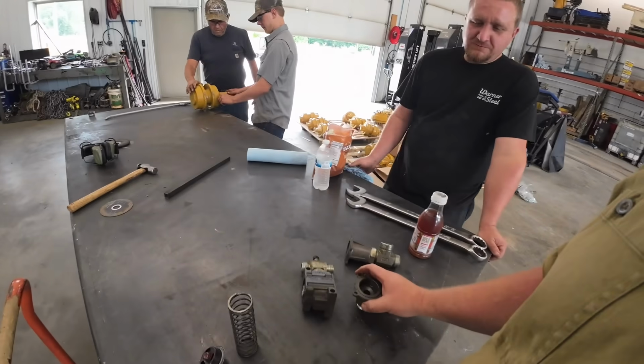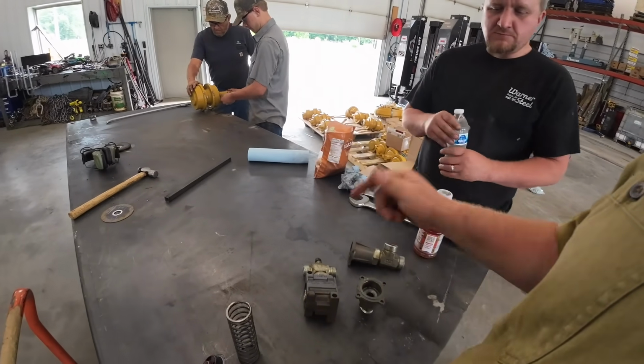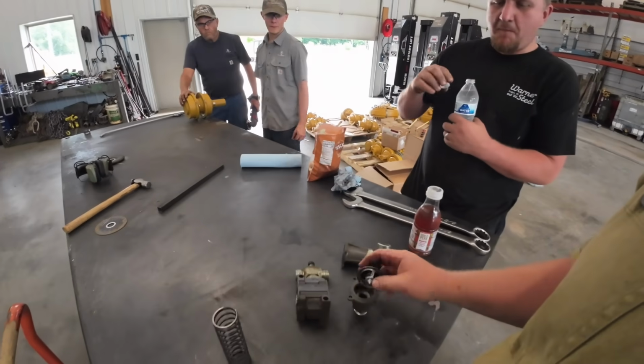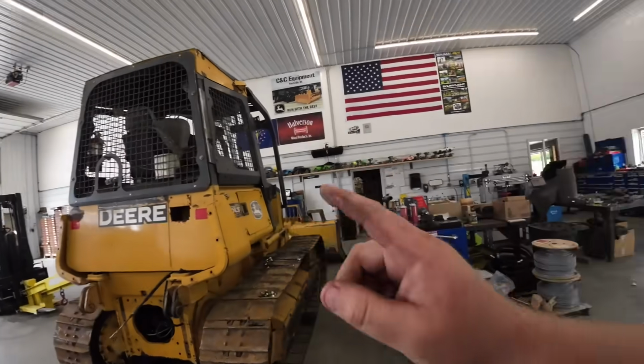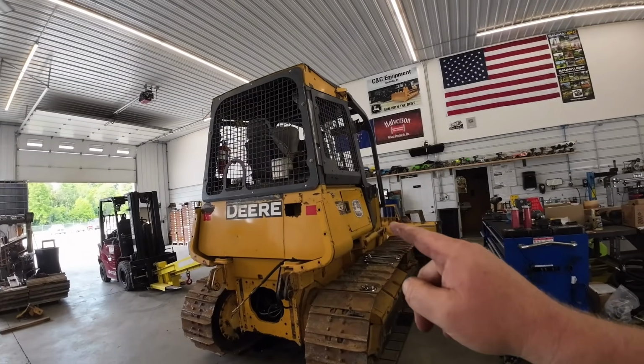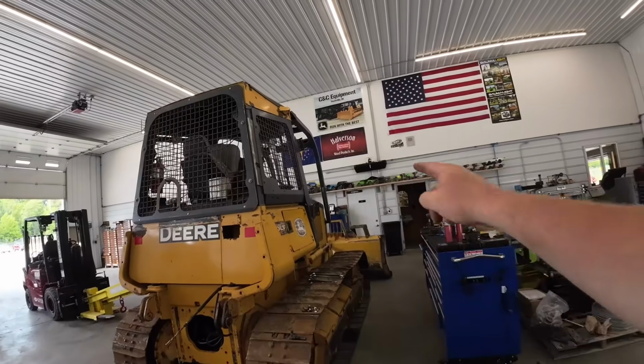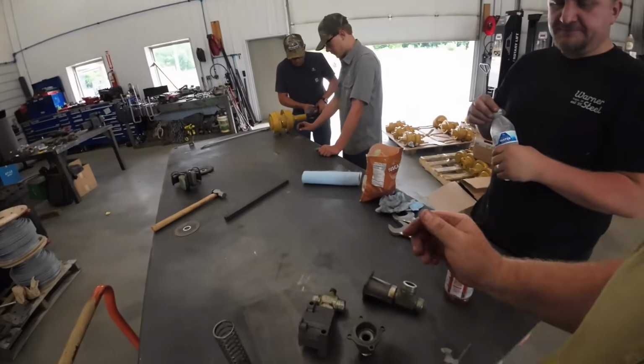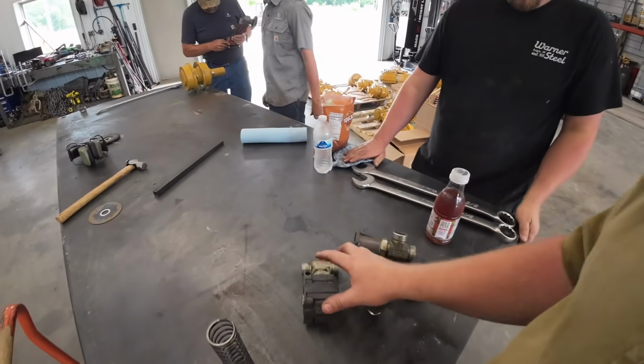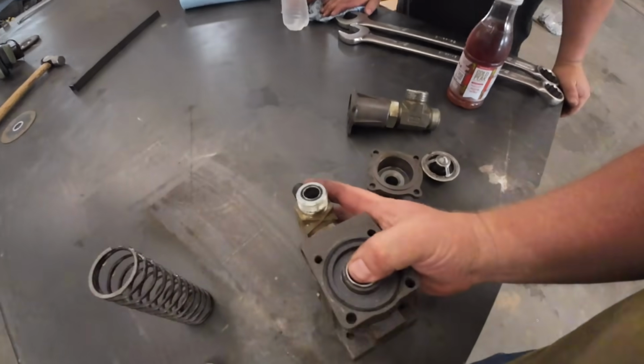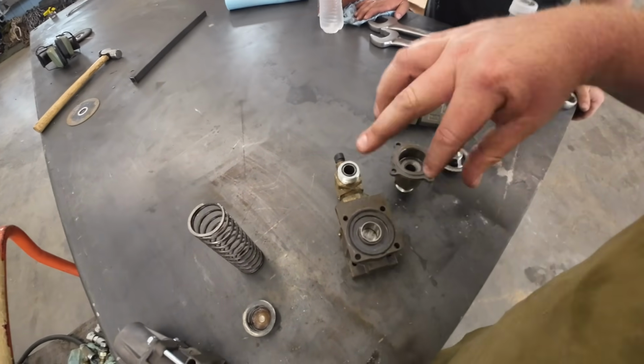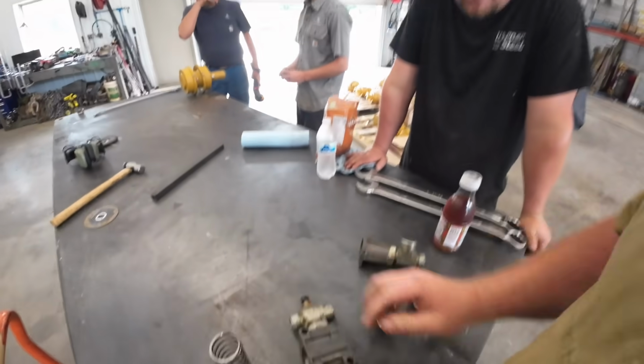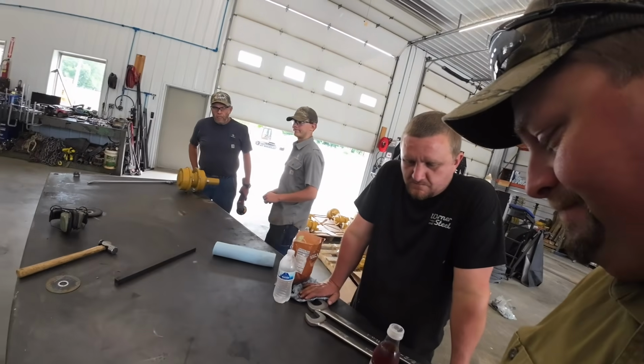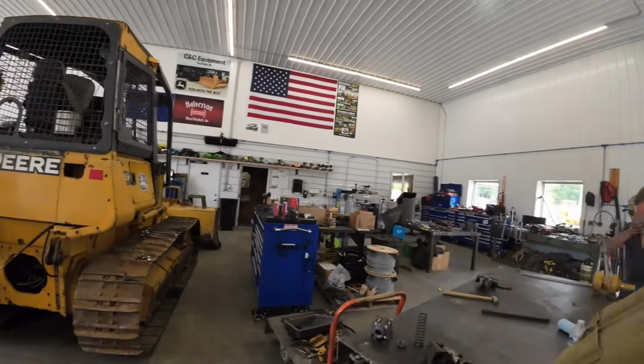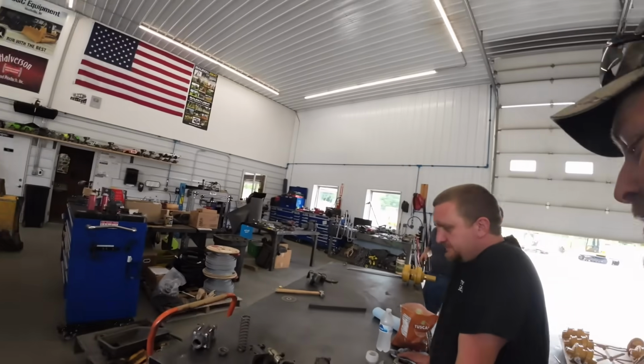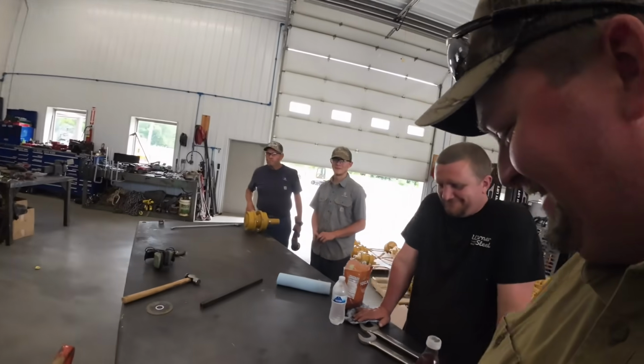There's a flow bypass valve for the oil cooler, and there's a thermostat in here. Basically, it sends oil to the tank until it gets to 140 degrees. Once it hits 140, it opens up and starts sending oil to the cooler in front. So when it's cold, this thermostat's closed. There's a bypass valve right here that had come apart, turned sideways, and was sticking, so it wasn't letting oil back to the tank. Since the oil couldn't go back to the tank, it had to go somewhere - hence the case busting on the new pump again.